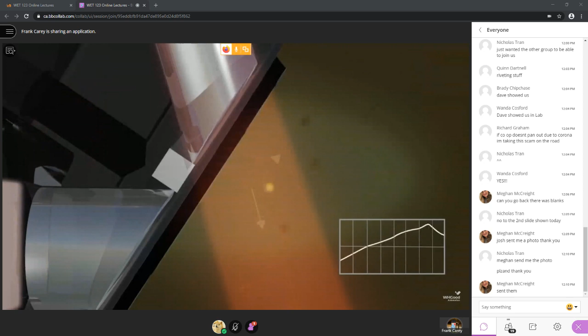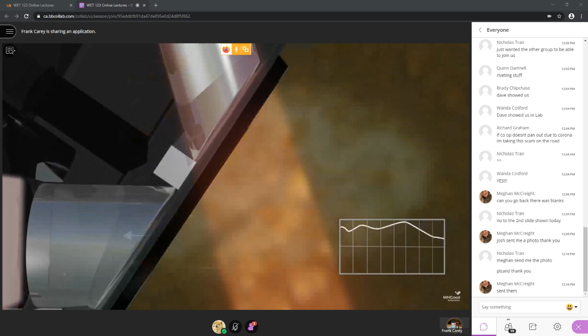The light beam is scattered by particles in the sample, and the scattered light intensity is measured by the sensor's photodetector positioned at 90 degrees to the light beam. The scattered light detected by the sensor is directly proportional to the turbidity of the sample.